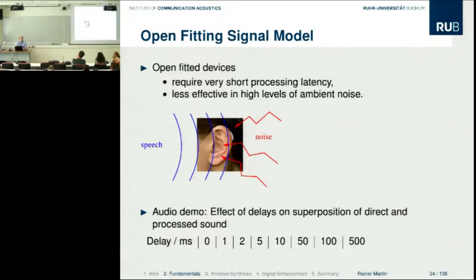The latency, the delay. Typically you try to keep the latency below 10 milliseconds, because above 10 milliseconds you start to have really these reverberant impressions, these reverberant effects. So hearing aids are designed to provide a latency not larger than 10 milliseconds.